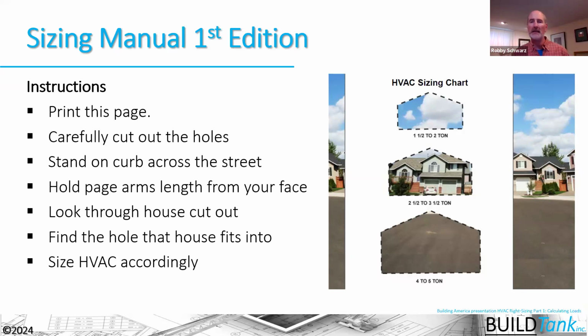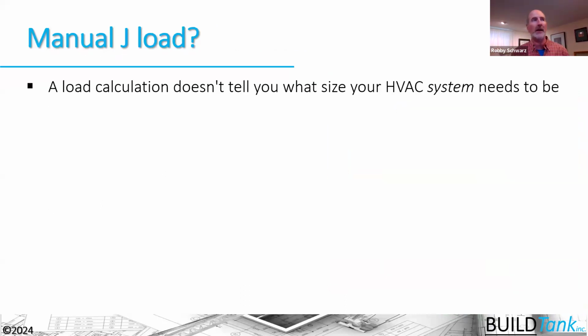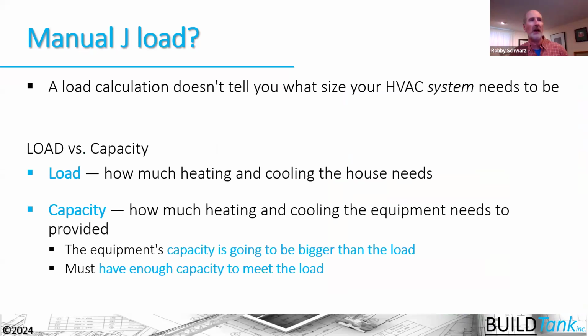But as we right size the equipment, we have to always remember the linkage of the HVAC design to the building thermal envelope. So this is all an integrated system. It's all the synergy where all these parts are coming together to achieve something that they couldn't achieve on their own. Therefore, we have to take each part of the system very seriously and ensure that they're all getting carried out, and carried out well. So a load calculation doesn't tell you what size HVAC system we need to install. What it does is it helps determine the capacity of that system that needs to be installed.